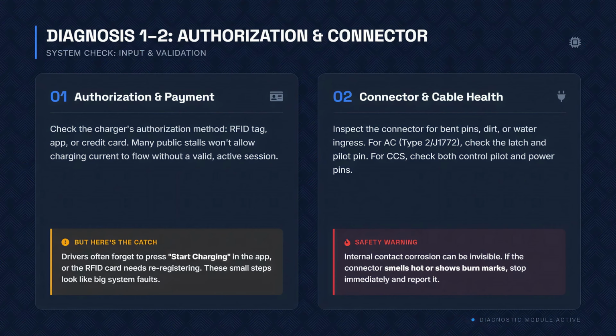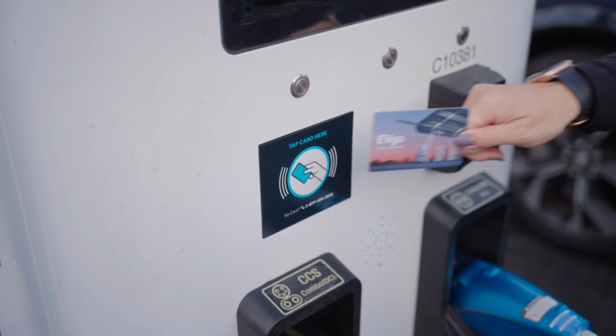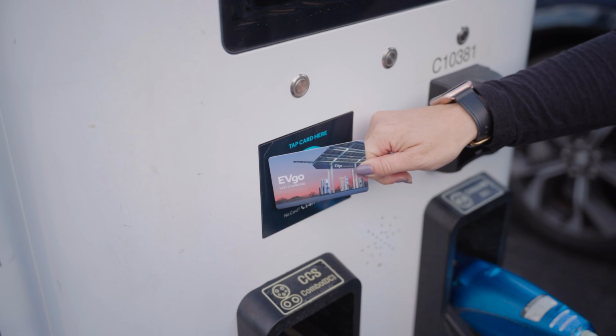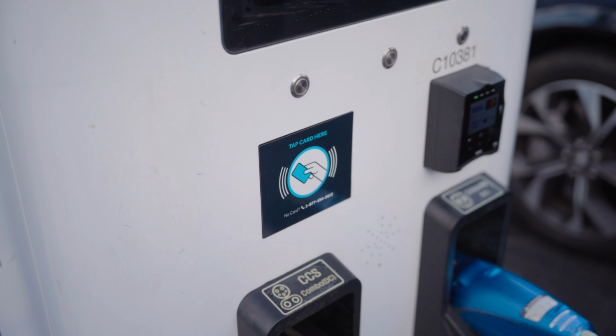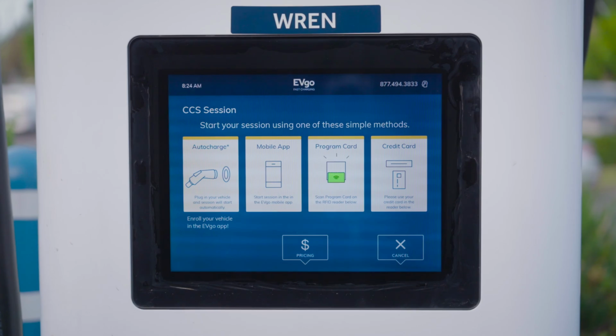Second, connector and cable health. Inspect the connector for bent pins, dirt, or water. For AC Type 2, like J1772, check the latch and the pilot pin. For CCS, check both control pilot pins and the power pins. But internal contact corrosion can be invisible. If the connector smells hot or shows burn marks, stop and report it to the operator.